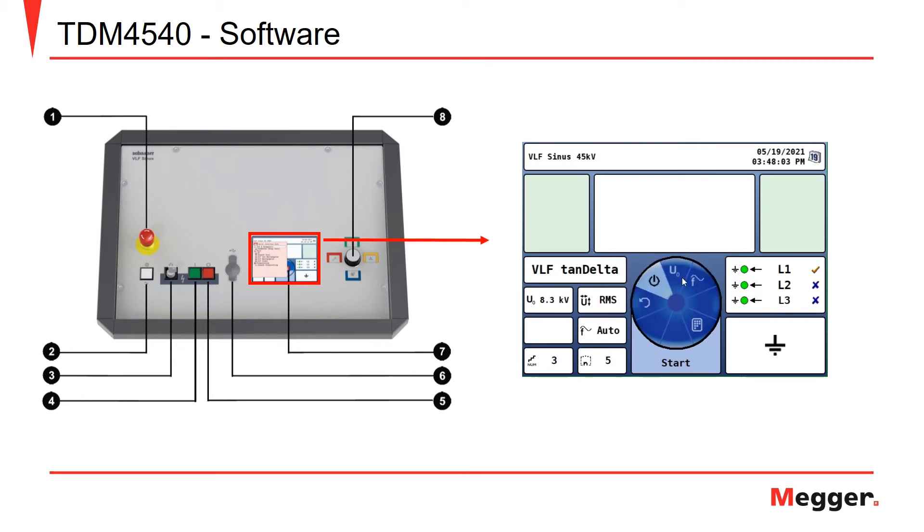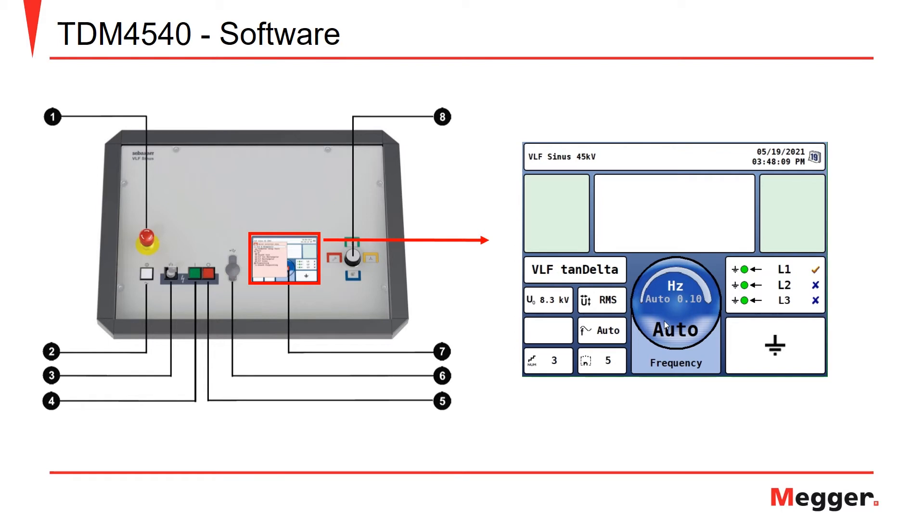We've already chosen U-naught. We can select our frequency. If we leave it in auto, this will choose the highest frequency that you can run the test at. Or, you can manually change the frequency, anywhere from 0.01 all the way up to 0.1 Hz.